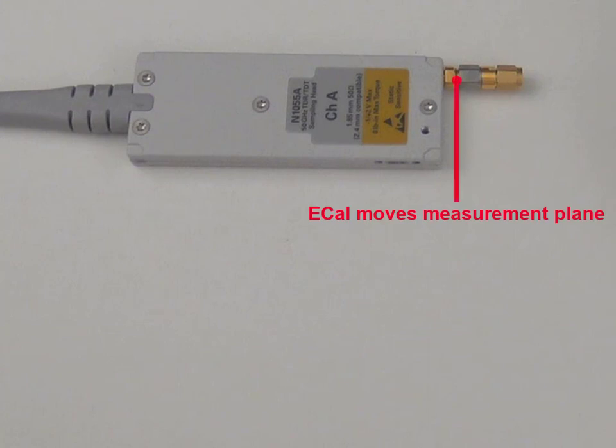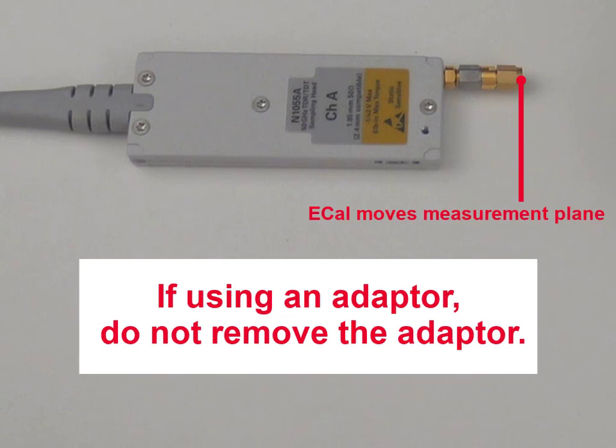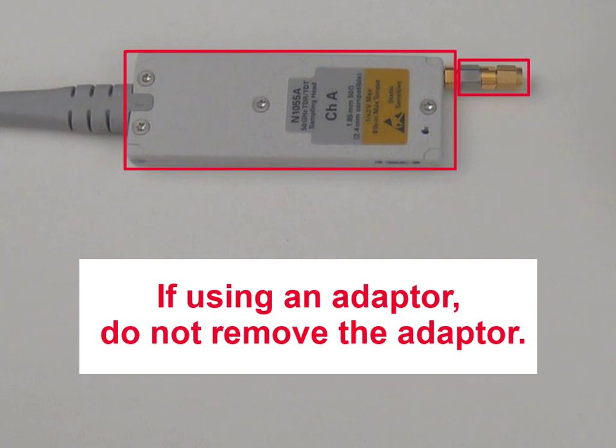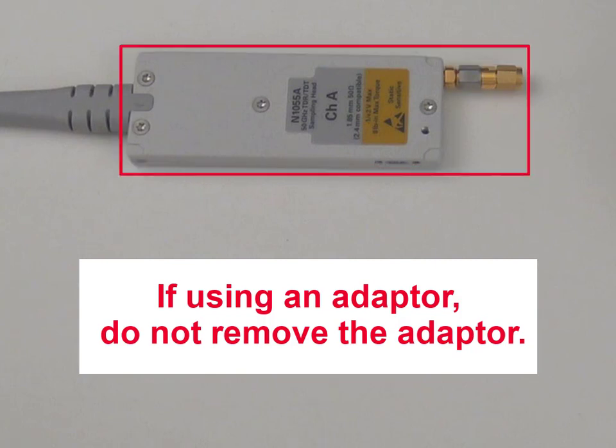Once you have used the eCal to move the measurement plane to the mate point of the adapter, do not remove the adapter. The adapter is now a part of the measurement head and removing it will ruin the calibration and any measurements.